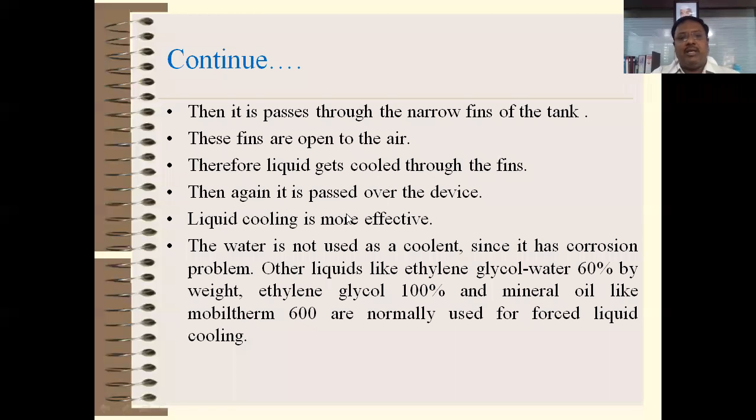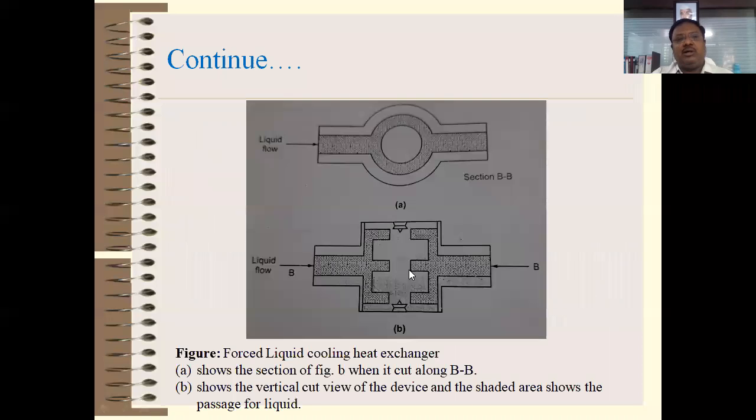Now the coolant or liquid that is used for this purpose is normally not pure water. It is water with some additional content, like ethylene glycol: 60% water and 40% ethylene glycol, so that the corrosion problem with the water is avoided, right? Because this water is continuously flowing through the tank to the fins, back to the tank, again fins, and so on, the fins and tank may be affected by the water. So pure water is not used. In place of pure water, some other materials are given, as shown here in front of you. So this is about forced liquid cooling.